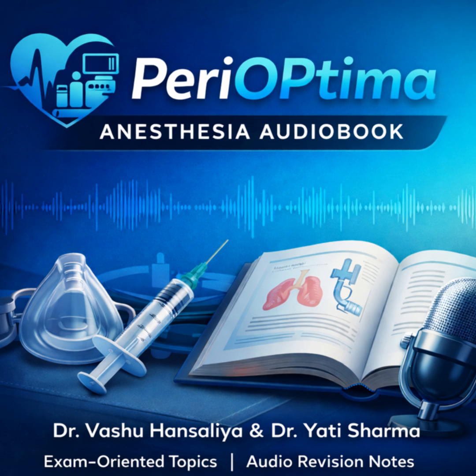This is the most vulnerable part of the machine. The low-pressure system starts at the flow control valves. It goes through those delicate glass flowmeter tubes, through the vaporizer manifold, and it ends at the common gas outlet, or CGO. The pressure here is very, very low, just slightly above atmospheric pressure. And why is that a risk? I would think high pressure is the risk.